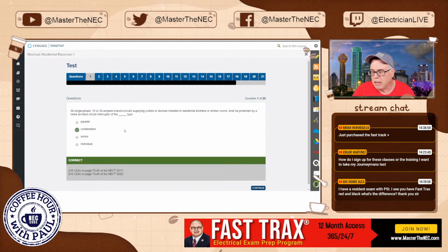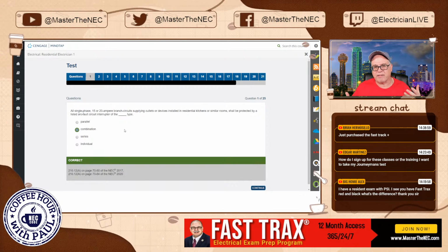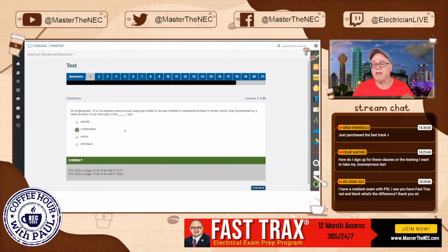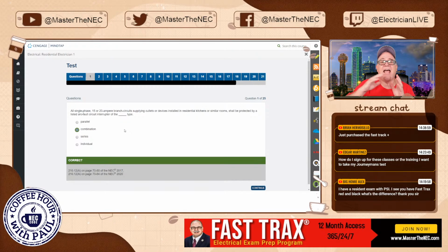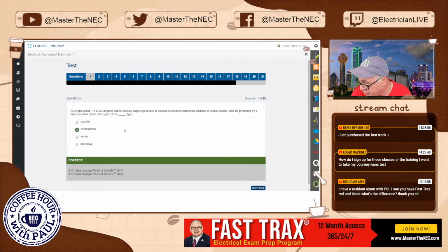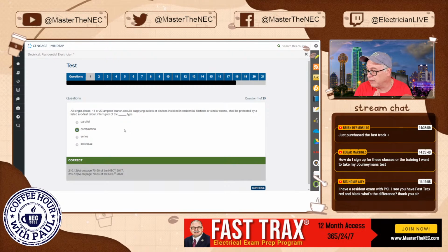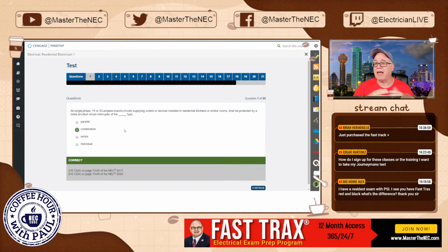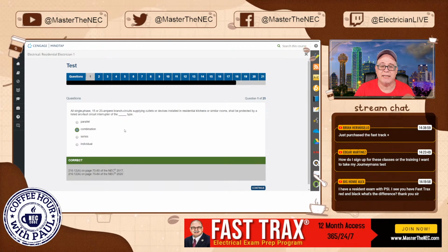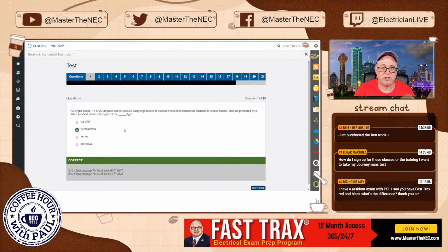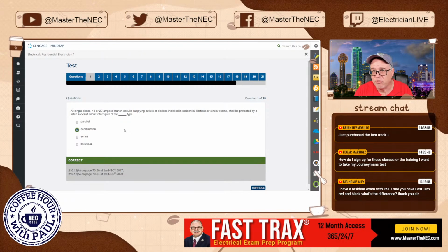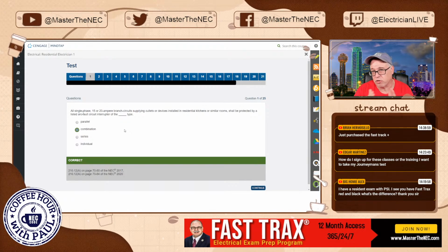With me? And so there's also these products out there called dual function. That is not a combination. A dual function is both GFCI and AFCI. Two different technologies that work very good together, okay? Not to be confused, okay? So again, a lot of people will call one of those arc fault and GFCIs a combination, and that is not correct. It's dual function. It's doing multiple functions. Combination is looking for two different types of arcing characteristics, okay?